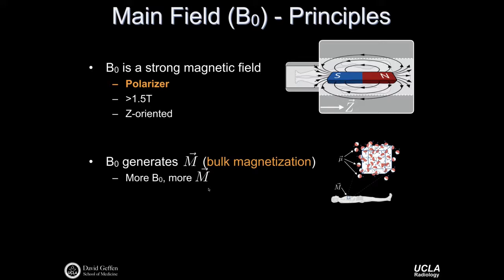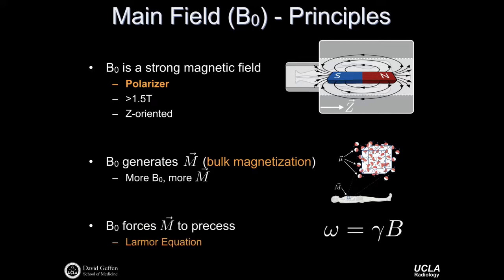The more available magnetization, the stronger the signals for forming higher quality images. B0 forces the bulk magnetization to precess according to the Larmor equation. If we know the strength and direction of the externally applied magnetic field and the gyromagnetic ratio of the species of interest—in our case typically hydrogen—we know the Larmor frequency at which the spin system will precess. This is critical because many things rely on knowing the Larmor frequency for both exciting the spins and forming images.